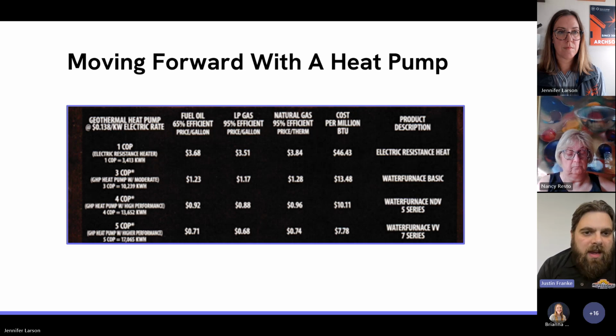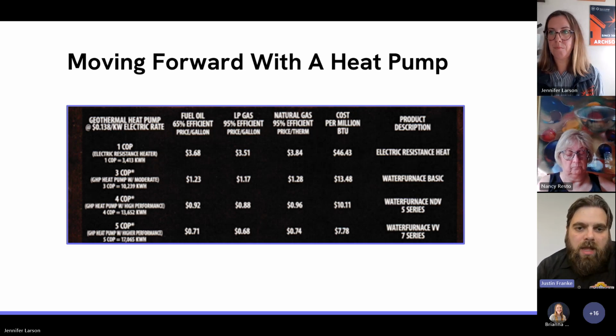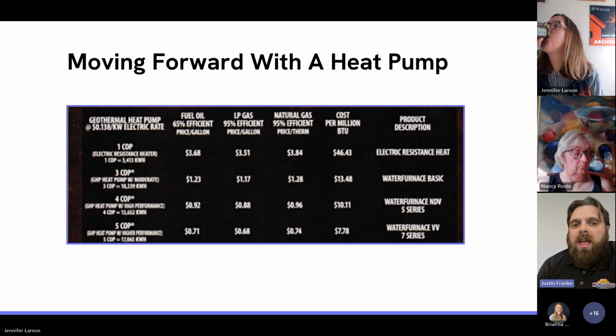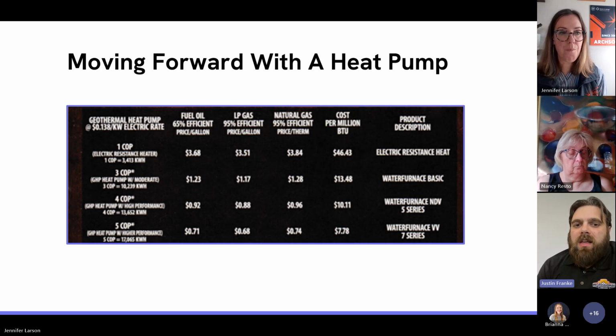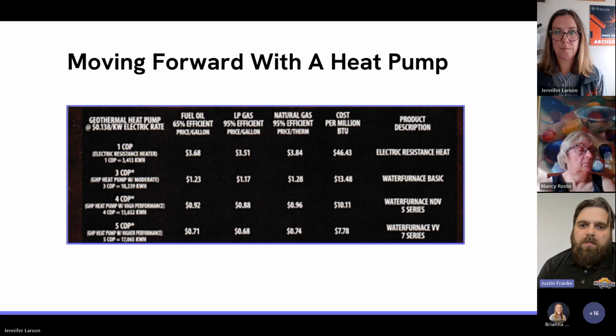Right now at a COP of 3, which is our air source, you'd have to be purchasing your LP gas at under $1.17 a gallon. Right now LP gas is running right around $1.80 a gallon, so that's 70 cents difference. When you get down to a COP of 5, we'd have to purchase our LP gas for under 68 cents a gallon - I don't think that's even been in the realm of possibilities in the last 10, 15 years. So that's kind of the cost comparison.